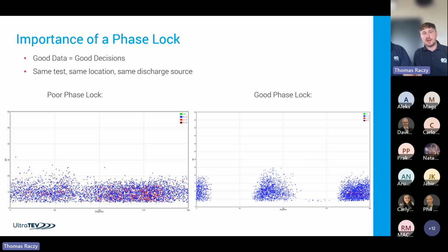On the left-hand side, we've got absence of phase lock. You can see the pulses drift to either the left or right-hand side of the screen, and effectively what's created is a continuous signal across the power cycle, loads of dots across the power cycle, which, as we know, has nothing to do with PD, because we mentioned PD occurs on the rising positive edge and rising negative edge of the power cycle. On the right-hand side, we've got correct, good phase lock, and you can clearly see two groups of discharges. Actually, what you're looking at is probably three groups, but bear in mind that the group closer to the zero crossing point actually belongs to the last group. So it's still two groups separated by 180 degrees.